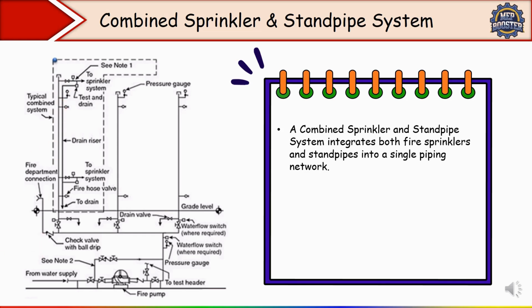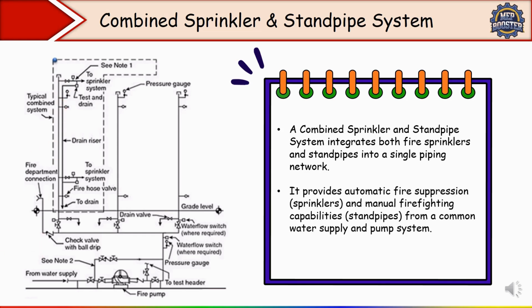Okay. So it provides automatic fire suppression, sprinkler and manual firefighting capabilities from a common water supply and pump system. That is called as a combined system. Okay. Is it clear? So combined system uses the same piping and pump for both sprinkler head and fire hose connection, means the standpipe. And it reduces the cost and simplifies maintenance. Okay. So it is common in high-rise building.